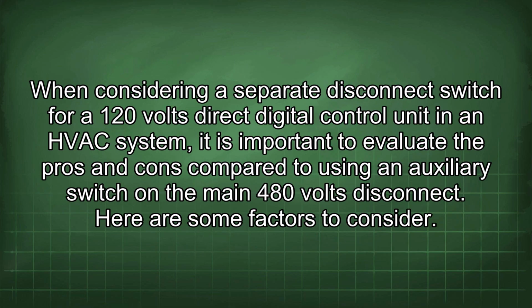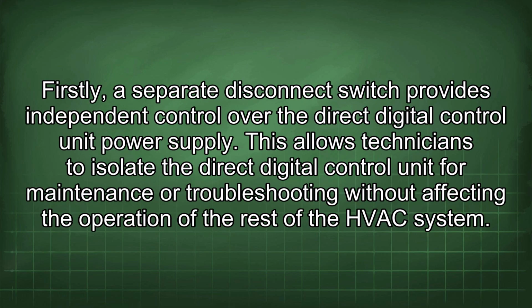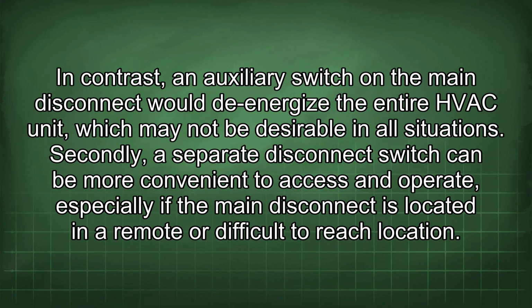When considering a separate disconnect switch for a 120 volts direct digital control unit in an HVAC system, it is important to evaluate the pros and cons compared to using an auxiliary switch on the main 480 volts disconnect. Here are some factors to consider. Firstly, a separate disconnect switch provides independent control over the direct digital control unit power supply. This allows technicians to isolate the direct digital control unit for maintenance or troubleshooting without affecting the operation of the rest of the HVAC system.